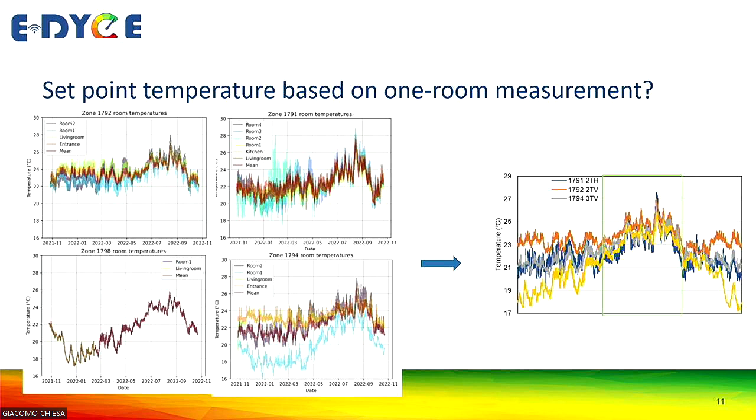And this is the case for that apartment, that apparently the temperature that we measure in that room is not representative of the average temperature in the apartment, and thereby the performance gap for the model in this case is increased. And the figure to the right, you can see here, is the average apartment temperature over the year if we average for each apartment separately.